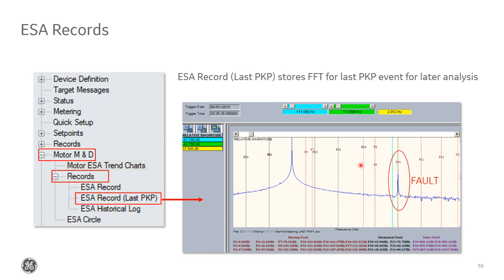If you did have a fault occurrence pickup, you can also see the last pickup FFT that was stored at the time of the event. This screenshot is a case where we were actually using a test set to simulate a fault, so the signal looks pretty clean, but you would see something really similar to this where if there's a fault, that fault frequency magnitude value would show up as a pretty big spike. Again, you can save this to the file. You can save this as a CSV file if you want and graph it elsewhere or screenshot it like we did here.